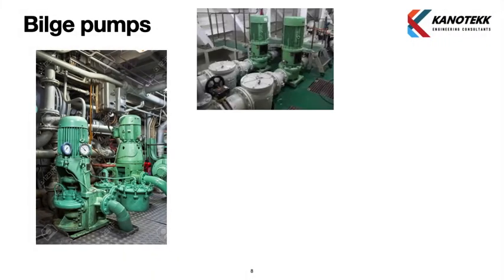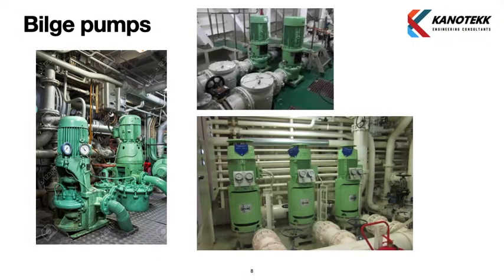Bilge pumps are centrifugal pumps with self-priming capability. In offshore jackup rigs, the capacity generally varies from 80 m³/hr to 140 m³/hr, and the head varies from around 40 meters to 60 meters, depending on the rig design.